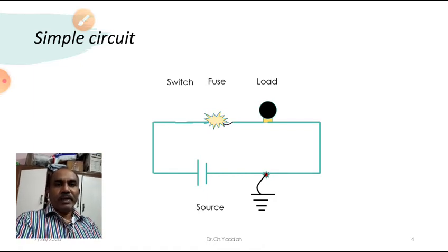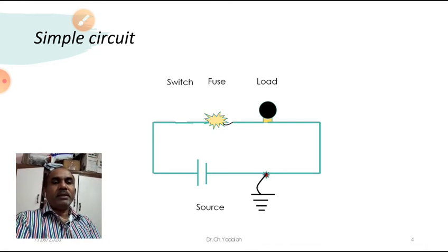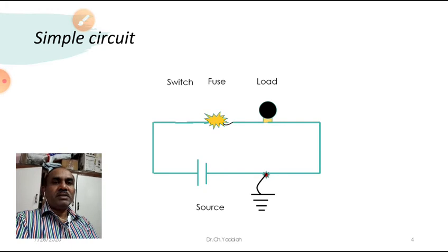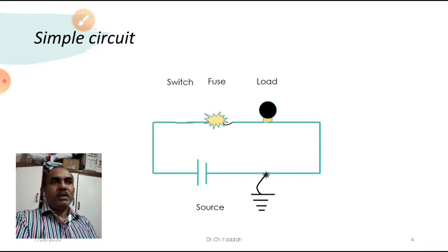Less than 1 ampere. If a line which is carrying hundreds of amperes at high voltages is suddenly chopped, then it creates a large amount of arc. The arc may reach a high temperature, above 3000 degrees centigrade. This temperature easily melts the contacts on both sides. So what will happen? Next we are going to have to replace that equipment.